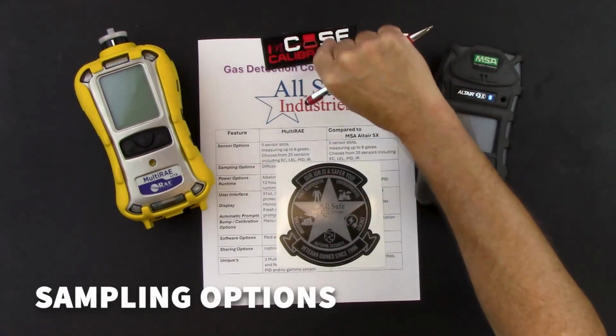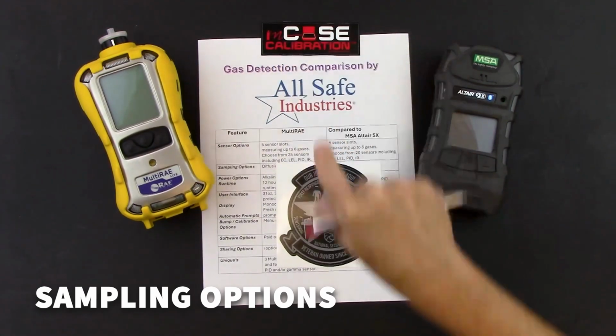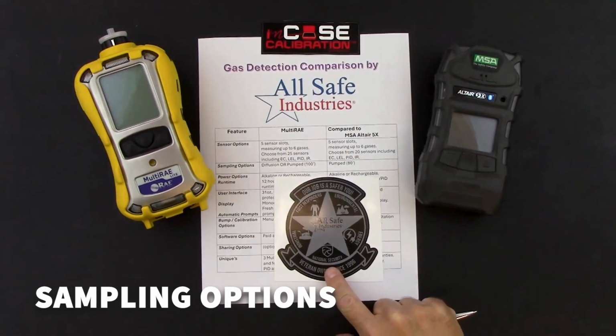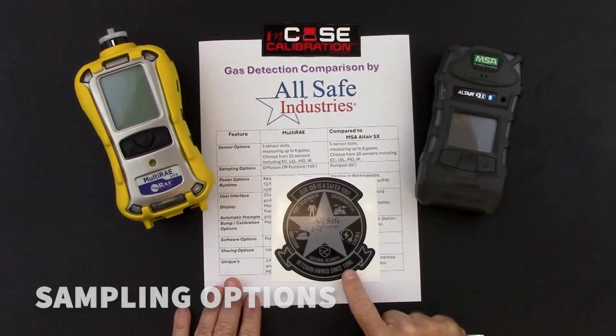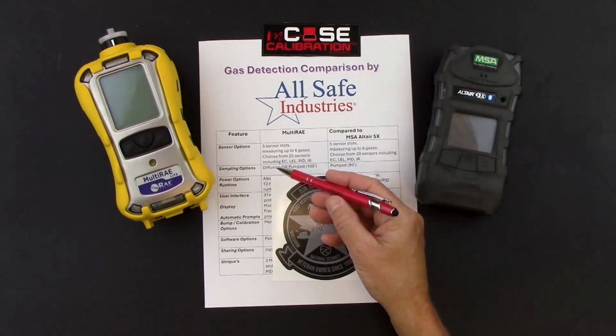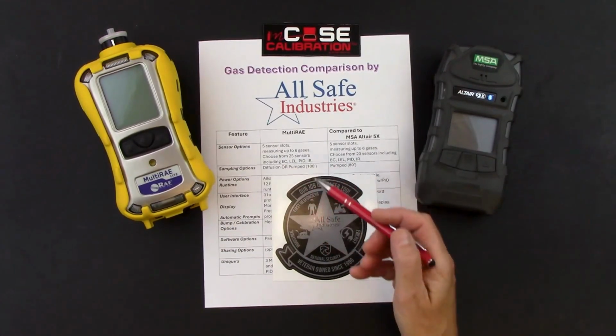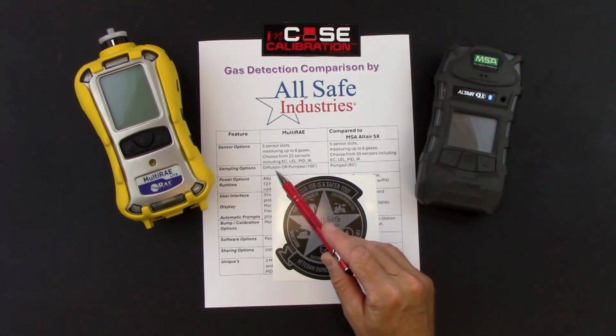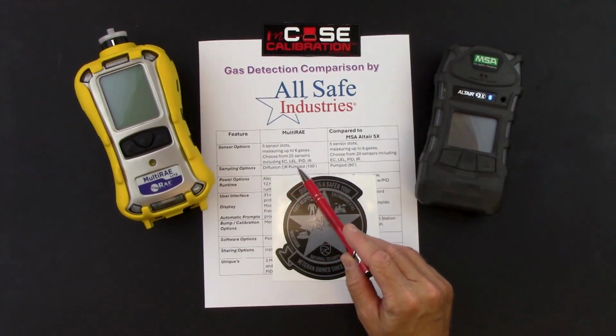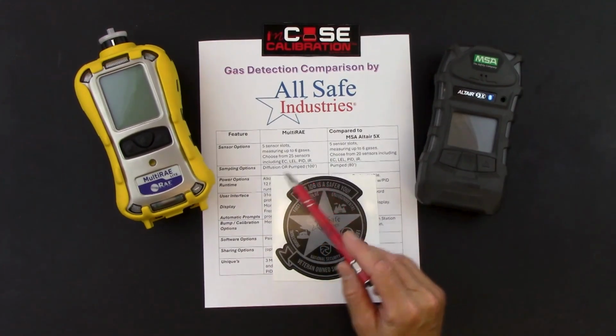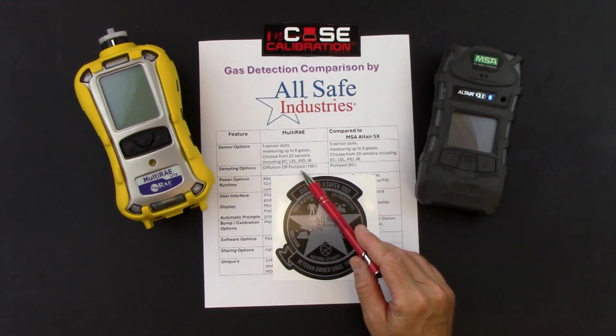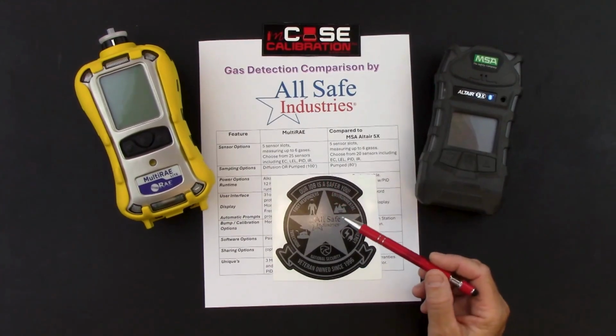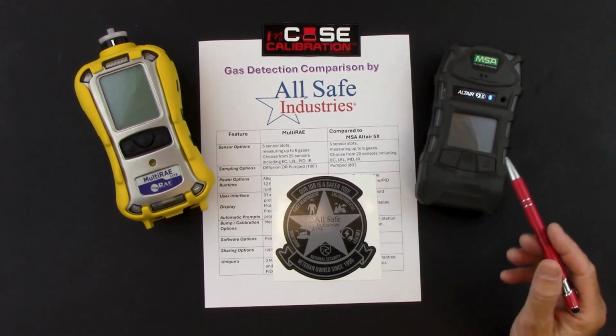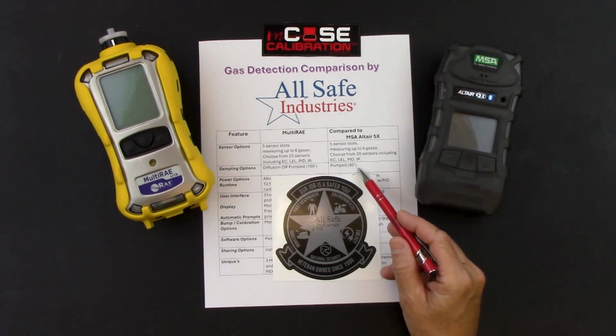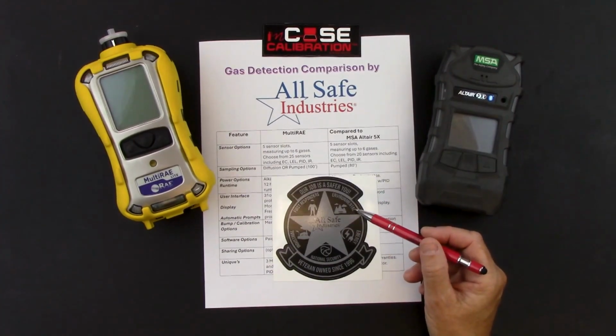For our sampling options, our choices on the MultiRAE are diffusion or pumped. So there is a version of the MultiRAE Lite you could purchase as a diffusion instrument, but not if it has a PID. It would need to be pumped, and then all the other models of the MultiRAE are a pumped version, and they can pull through 100 feet of tubing. The Altair 5X is a pumped instrument, and it can pull through 80 feet of tubing.